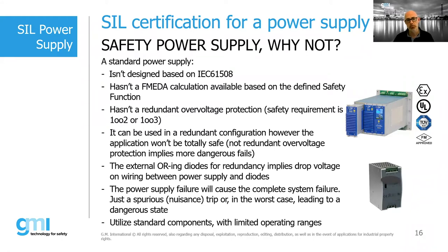And again, a standard supply system can be used in a redundant configuration, but it does not guarantee that our application is totally safe, for reasons related to the common fault which we have seen previously. Also, standard power supplies often require external ORing diodes to allow for redundancy. This means adding external wiring that, especially for high load currents, creates a high voltage drop which has a strong impact on the supply voltage. It's true that it's possible to adjust the output voltage to compensate for the voltage drop, but this operation increases consumption considerably.